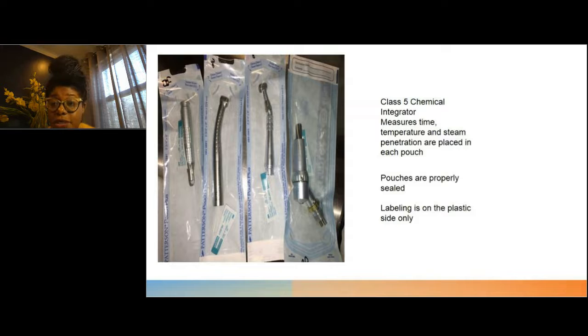And steam penetration. So what's happening to that instrument on the inside? Was the steam in the autoclave sufficient to kill the microorganisms? This information we find with biological testing, but the reason why it's important to put the indicator on the inside of that pouch is because inside is what matters.